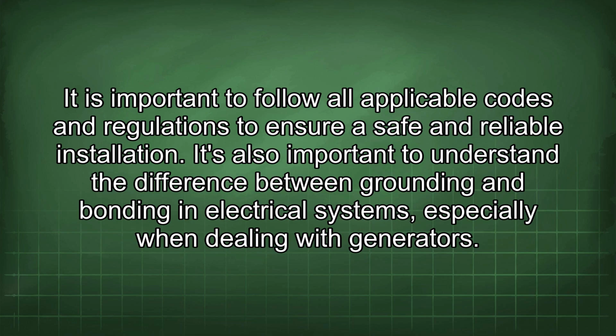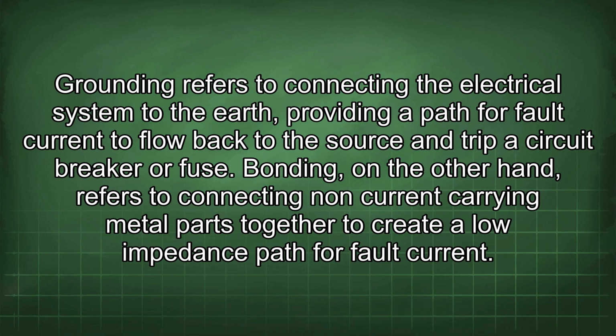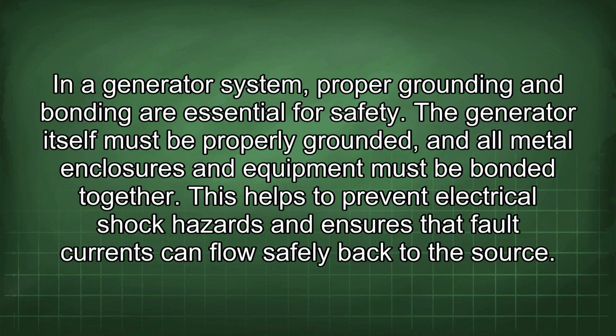It's also important to understand the difference between grounding and bonding in electrical systems, especially when dealing with generators. Grounding refers to connecting the electrical system to the earth, providing a path for fault current to flow back to the source and trip a circuit breaker or fuse. Bonding, on the other hand, refers to connecting non-current carrying metal parts together to create a low impedance path for fault current. In a generator system, proper grounding and bonding are essential for safety.